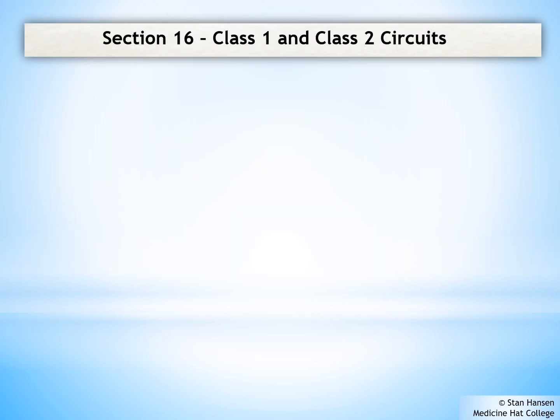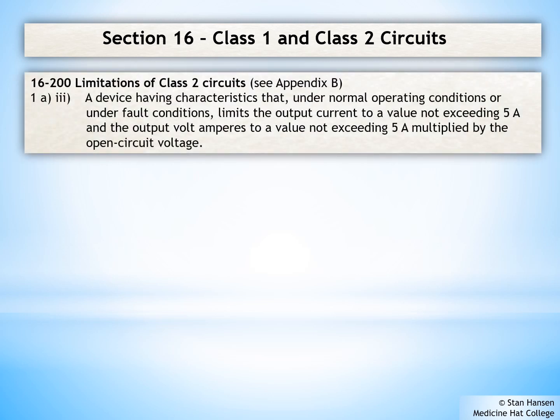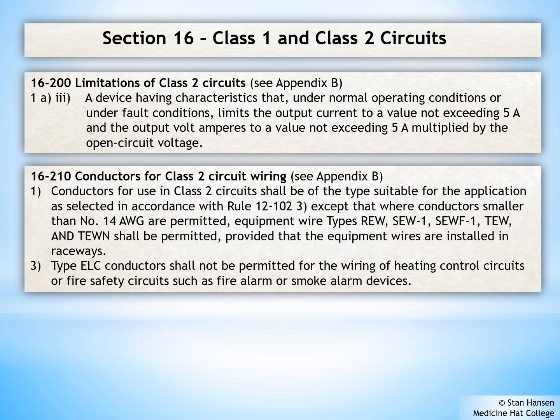Since my furnace not only employs 120 volts, but it employs 24 volt circuits, we also have to be aware of the rules on Class 1 and Class 2 circuits. 16200 tells me about limitations of Class 2 circuits. Any Class 2 circuit is limited to 100 VA, which means if I have a 20 volt circuit, it can operate at not more than 5 amps. Normally, the transformer inside the furnace is a 100 VA transformer, which does that limitation for me. When it comes to the conductors I can use for my Class 2 wiring, I need to make sure that they're properly approved according to Table 11. Typically, LVT cable is approved for use in Class 2 circuits, such as thermostat controls, doorbells, security systems, and other low voltage remote control systems, as long as we do not exceed 30 volts.